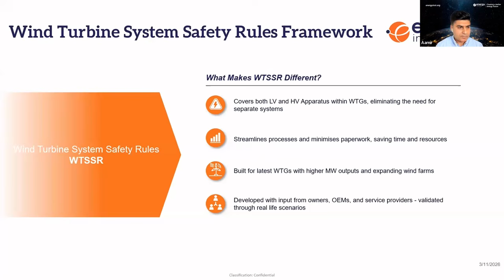In the next few slides I'll give a quick high-level comparison between the safety rules and the system safety rules. On the left-hand side, in blue, is wind turbine safety rules; on the right, wind turbine system safety rules. They've been designed in accordance with IEC standards, where low voltage is defined as voltage up to and including 1000-volt AC and 1500-volt DC. In the wind turbine system safety rules, high voltage is anything above that.